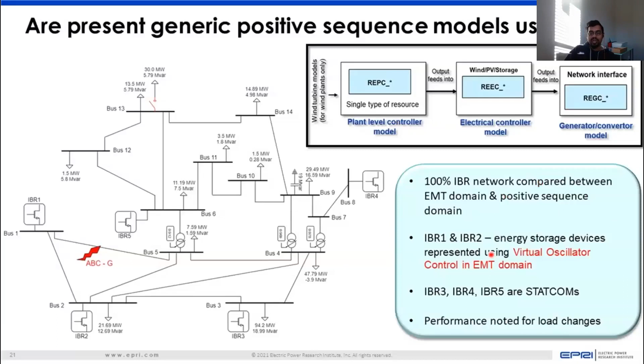So we looked back at the system with virtual oscillator control in the EMT domain, with a few StatComs in this 100% inverter-based resource network, and compared the performance of these generic models as they exist in software today. Software like PSSE, PSLF, PowerWorld, and Power Factory have these generic models available. We wanted to see if you can simulate a 100% inverter-based resource network and look at the frequency response characteristics using these models, comparing it with the advanced controls in the EMT domain.